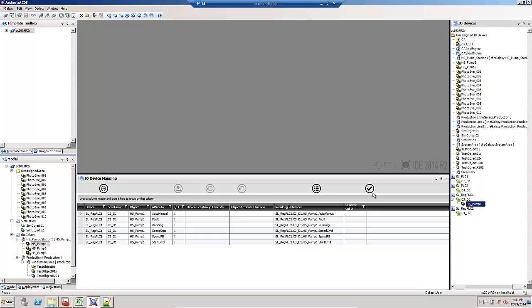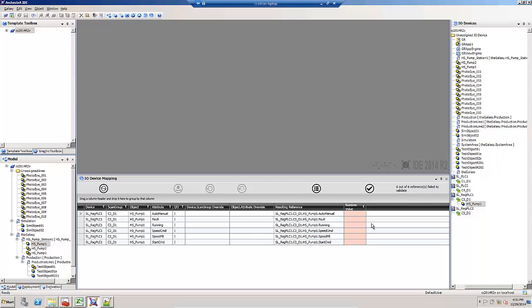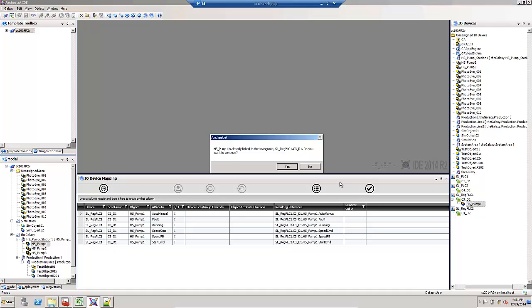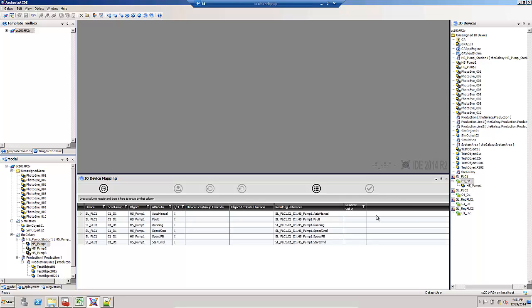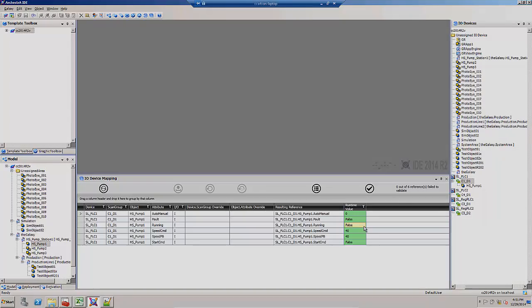They're showing in my I.O. mapping list. If I hit the validate, notice that they come up in pink and six out of six references fail to validate. At this point I can either override or assign them to the correct one. Once they're assigned correctly, they validate properly.